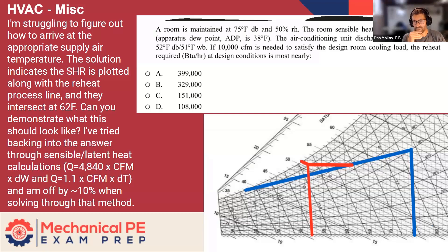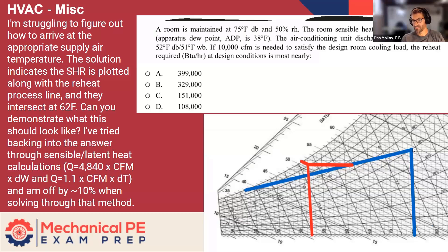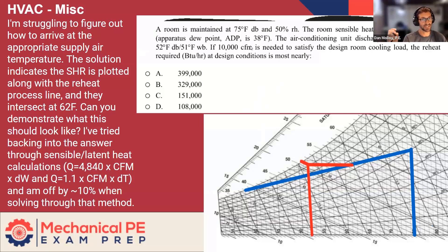I drew this on the psychrometric chart ahead of time. This drawing on the bottom is mine, an attempt to capture the given information and graphically solve for what they're describing in the written solution. The room condition we can find by going to 75 degrees and up to 50% RH — this point here represents the room condition. Then there's the room sensible heat ratio of 0.66. The best way to use this is the ADP. They've told you in parentheses that the apparatus dew point corresponding to that RSHR is 38.